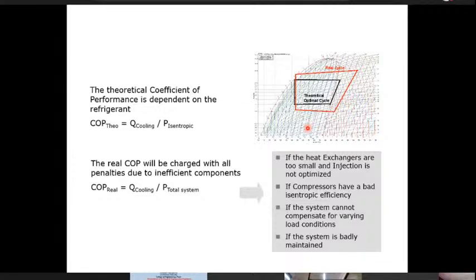So these are the four parameters. When we say heat exchangers are too small and injection is not optimized, in a heat exchanger we need to divide the refrigerant over several circuits. And those circuits need to be such that in every circuit the heat added is almost the same, so that refrigerant leaving every circuit is at a similar state. So we have a superheat that is close to each other. Now this is never possible to achieve practically an exact value of superheat because of the nature of distribution of air in practical systems. But the closer we have circuit by circuit superheat analysis, the more efficient a system will be. So when we are designing systems, we need to take care of this first part. Compressors we've discussed. Then this part we will discuss in the subsequent slides.